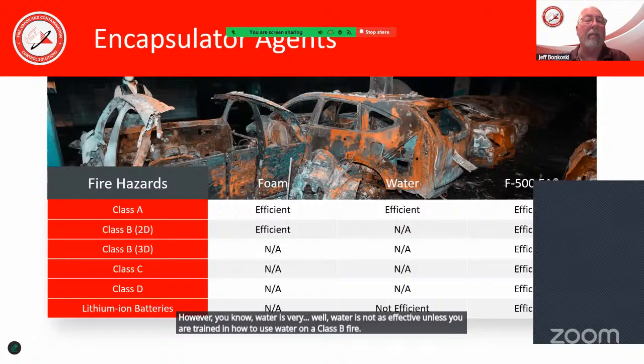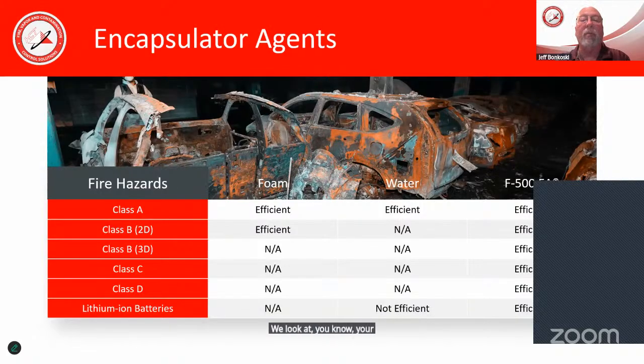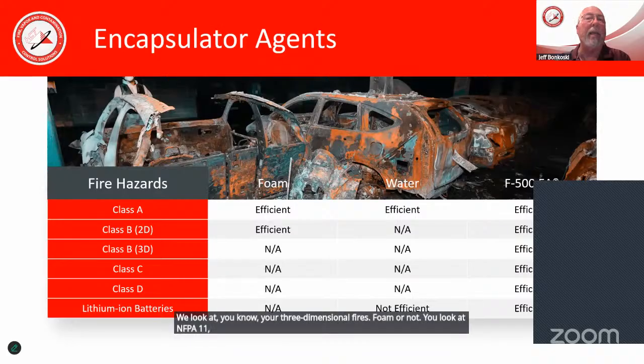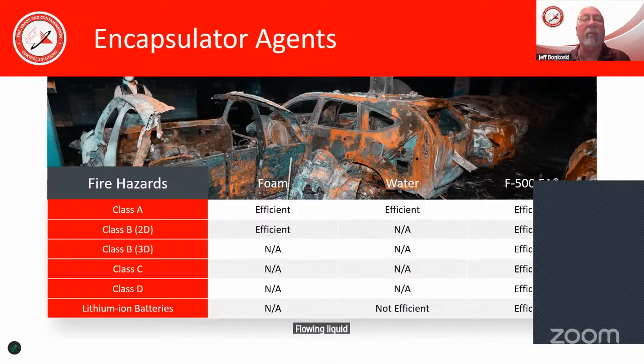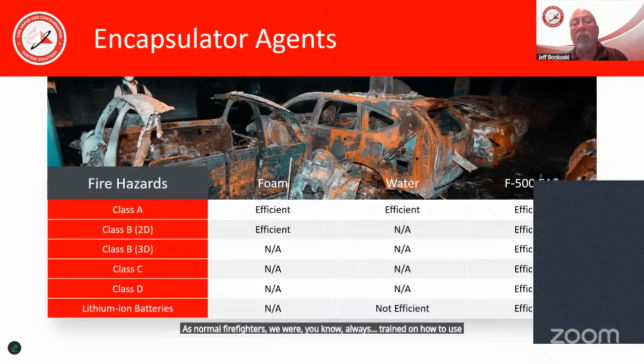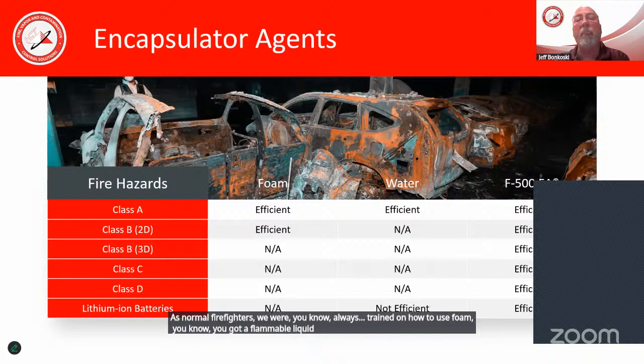Looking at three-dimensional fires, foam is not suitable. NFPA 11, Annex A11, even states that foam is not suitable for three-dimensional flowing liquid fuel fires or gas fires. But what have we always used? As normal firefighters, we were always trained: you got a flammable liquid fire, use foam.